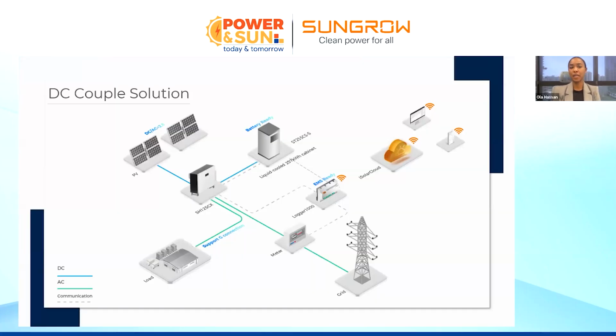Here is how a DC coupled solution will look. In the DC coupled solution, we have our PV panels connected to the hybrid inverter. The hybrid inverter will also have the battery connected on the DC bus bar. So it's a DC coupled solution. The battery will be connected to the inverter on the DC side. That's why with hybrid inverters, we allow a DC-AC ratio of up to 200%, because you are able to feed your load and at the same time charge your battery. That's why the hybrid inverters can allow up to 200% of DC-AC ratio.